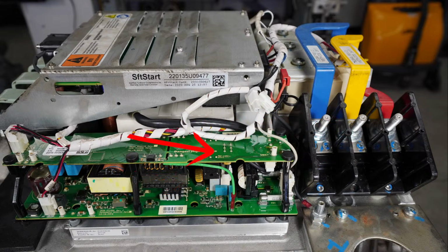So in your particular case here, with the question of not seeing anything power up, it's either an input power issue -- meaning we have power up here and didn't have a fuse blown -- or it's going to be a DC to DC converter issue. Those are the two most common things I have seen. Now, beyond that, we could spend quite a while here trying to work through every possible variable with these Turbocors, but those would be the two points I would want to start with and verify.